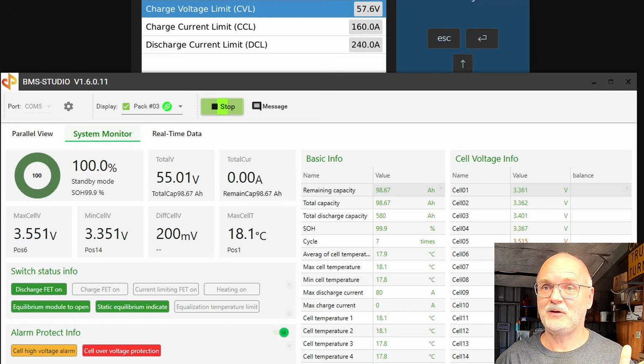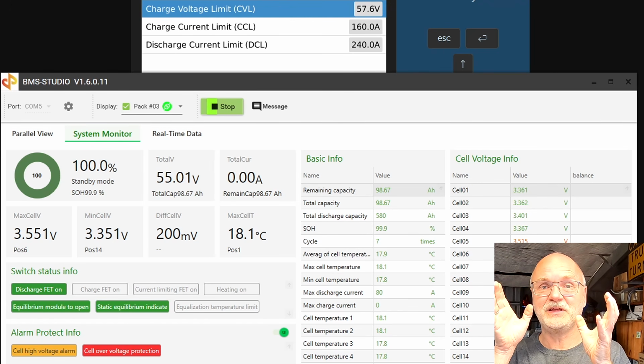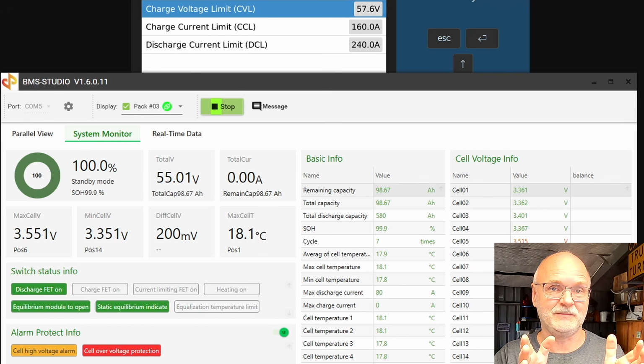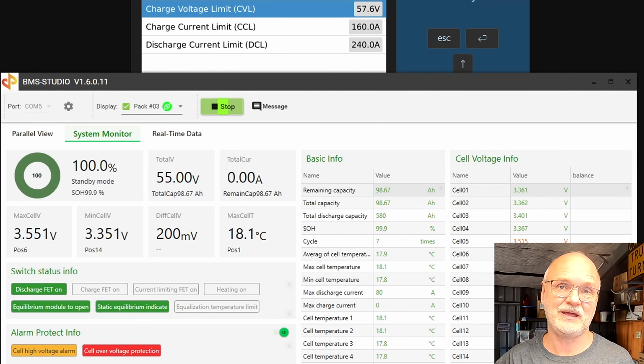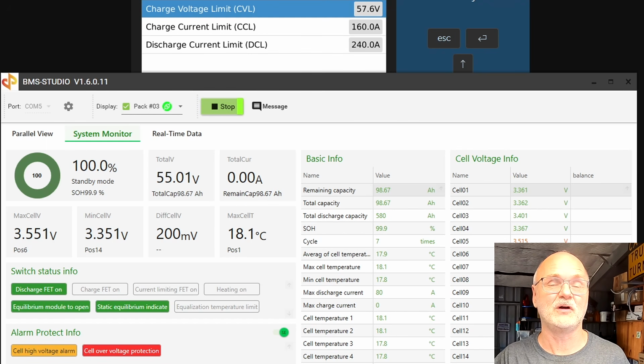If you have these batteries in parallel and the parameters and settings are different, it doesn't really matter. Each BMS is only looking after a single battery, pretty much the same as in my battery shelf with 3 different BMSs. If one of the batteries charges only to 55.2 and then disconnects due to over-voltage protection, or because we've reached the charge voltage, that battery will not be charged further.